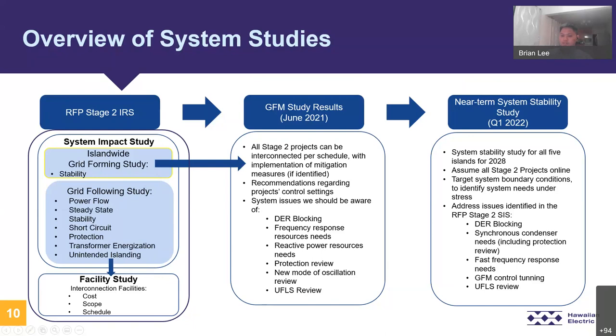So why did we need this EMT study in addition to the PSSE? At the time, we had concerns regarding the limitations of positive sequence simulations. For example, the accuracy of the PSSE simulations, uncertainty of IBR model response, and we were worried about potential control interactions between IBR. And simply because we didn't have the grid following models available on PSCAD, and we still don't have those available today from the developers.